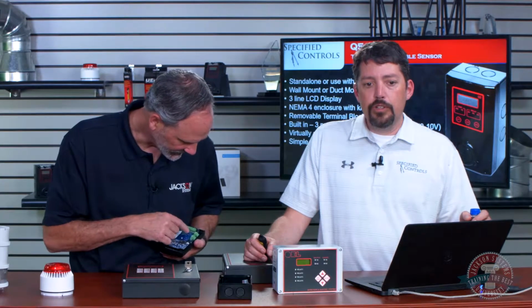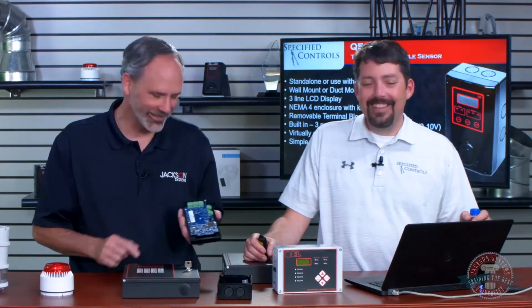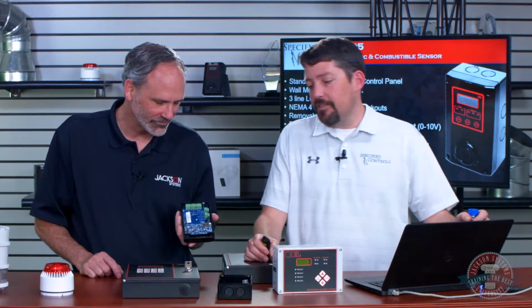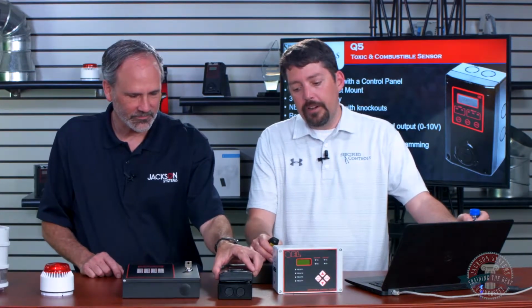They do have removable terminal blocks to make it easier to wire them. They have 3 built-in programmable relays and 1 0 to 10 output. Virtually any gas that you're going to come across is available. There are very few gases that you're not going to be able to use with this. And then it's just simple wiring and programming. There's not a lot to this in terms of being knowledgeable about it and wiring it up. So that's the sensor itself.